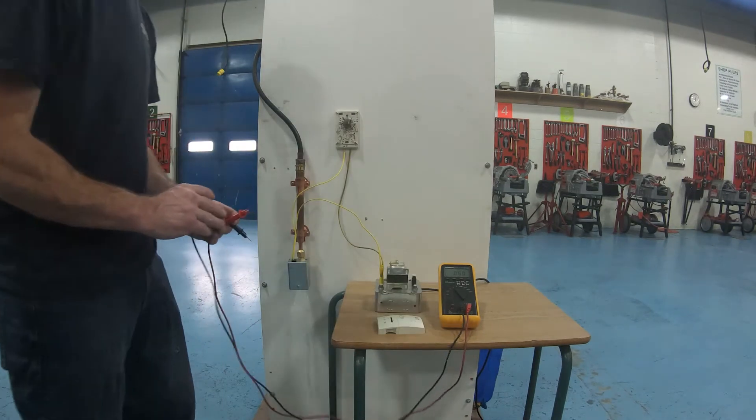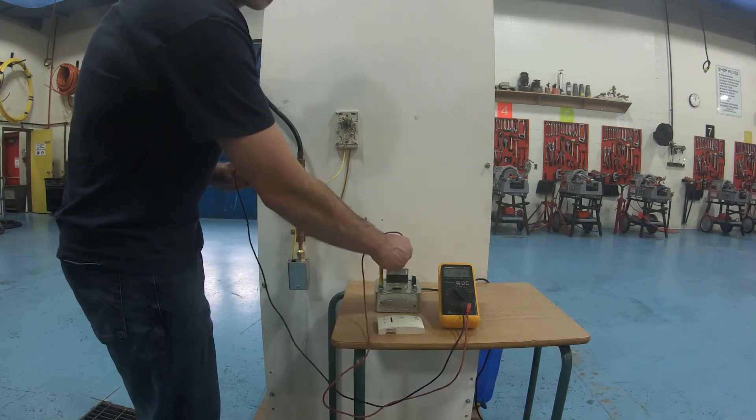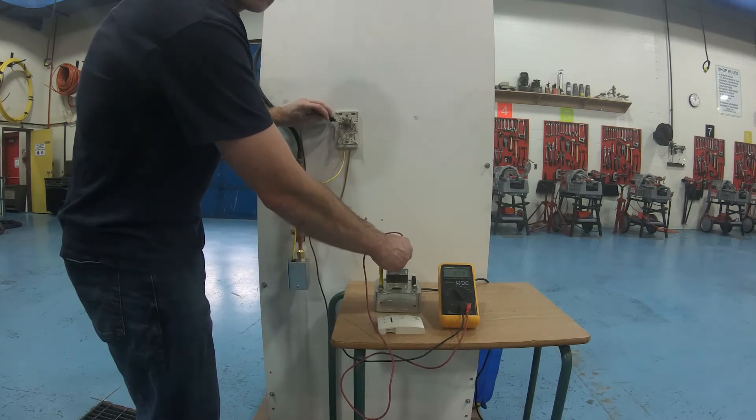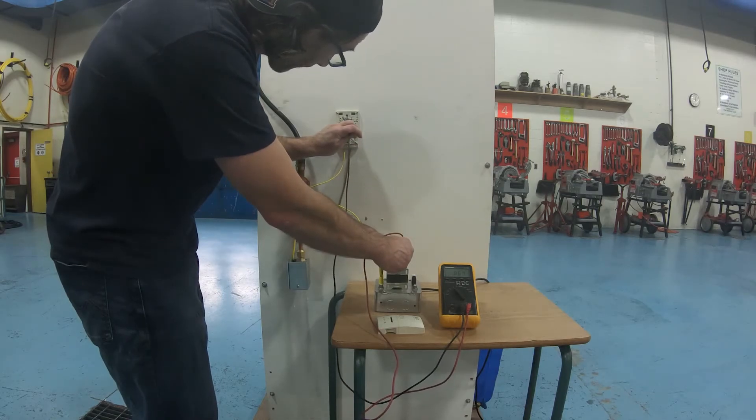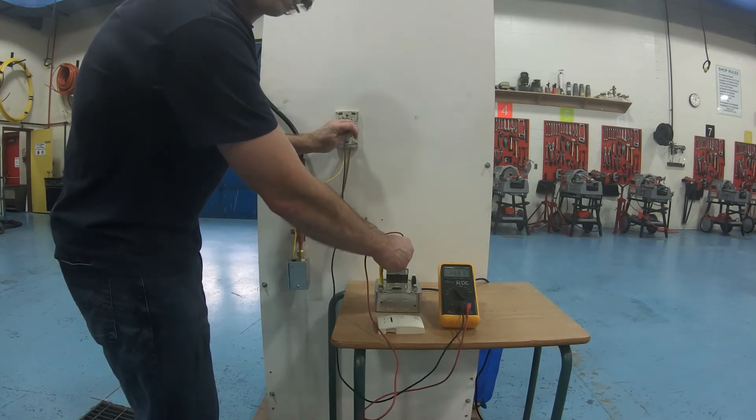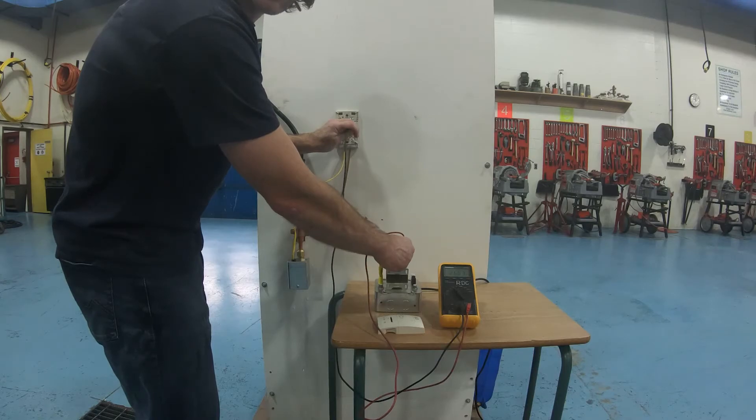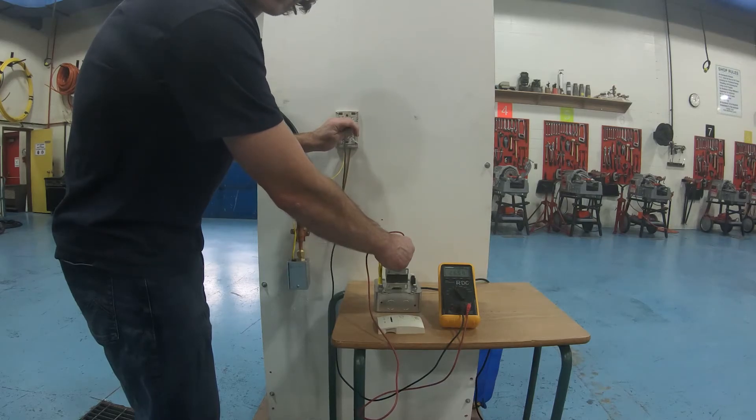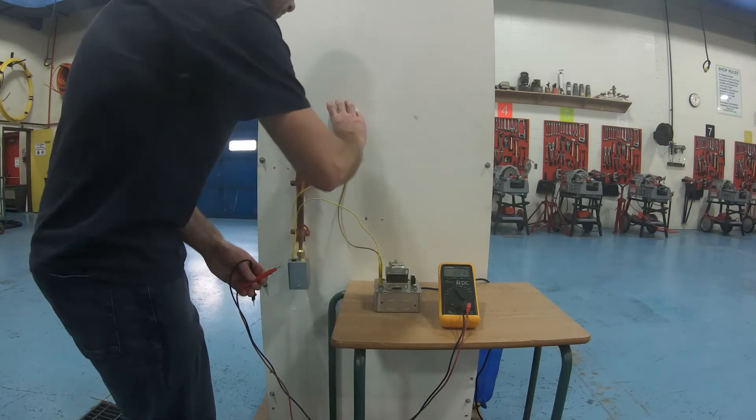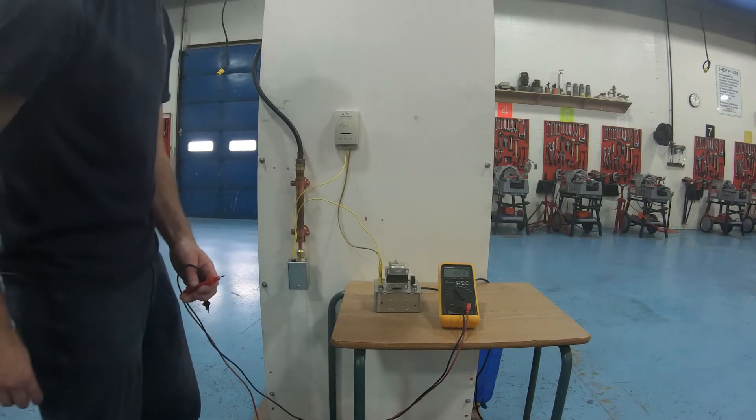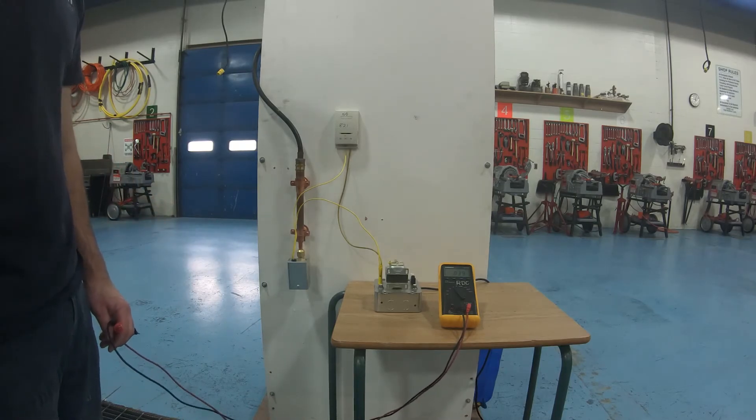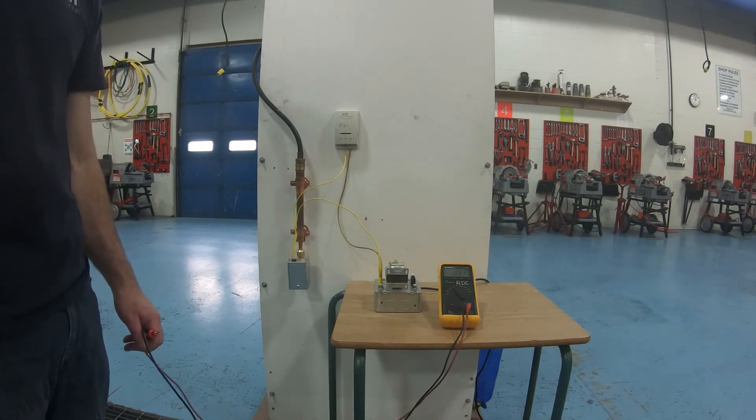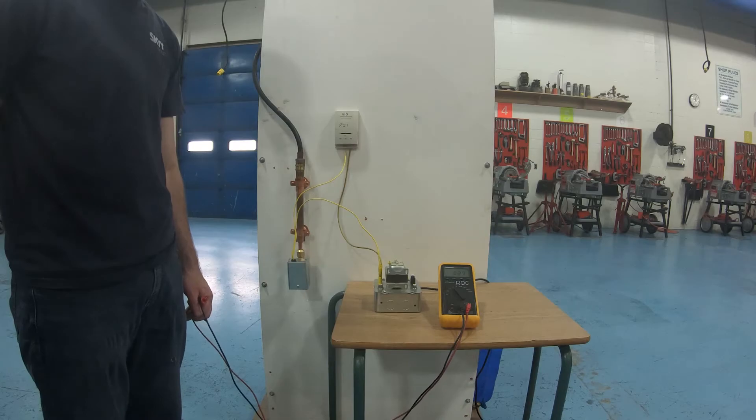Now what has happened is I've turned the power off to this zone valve here, and because it's a normally open zone valve, when it's powered down, water flows through it. So I will do the same test here. I've got zero. So as this is running, the way I can check this is I'm going to do the same electrical test. I'm going to go from this side of the transformer to here. I get zero volts, but when I move to the other side, I get 26.5. Hi, this is me from another dimension. What I was trying to say here is there's no power going to the zone valve, therefore the zone valve is open. All right, so we just simulated the heat being satisfied in the room. Zone valve now has full power going to it, 24 volts going to the zone valve, and it closes. So this is reversed of the other two types of zone valves.